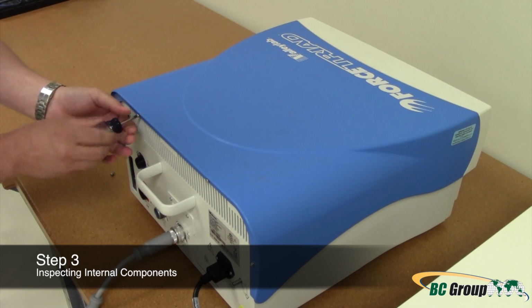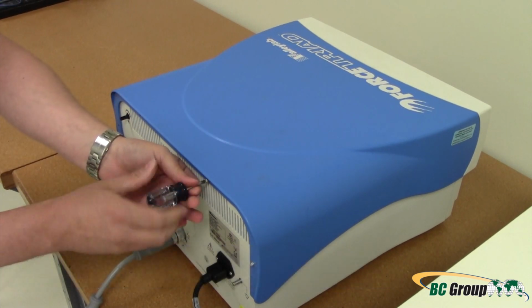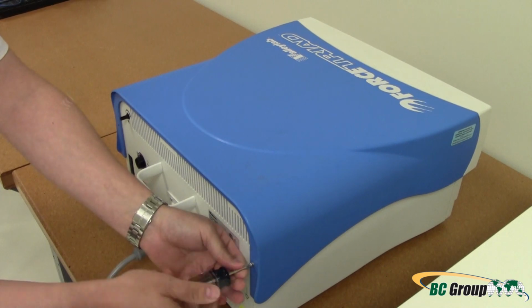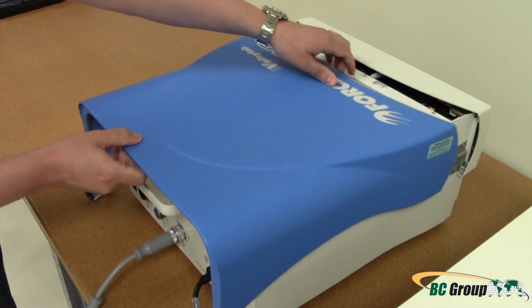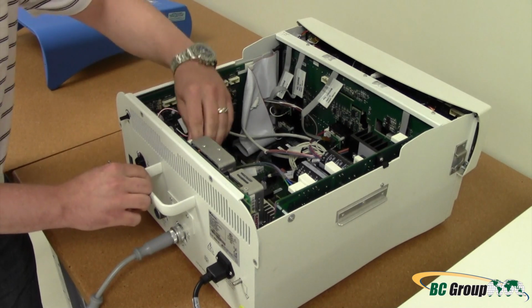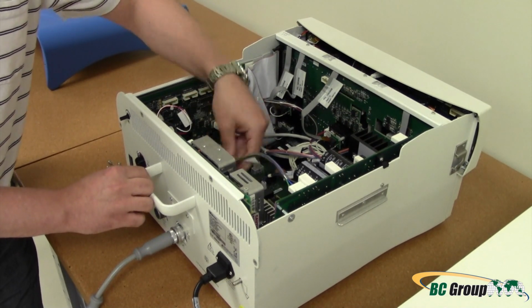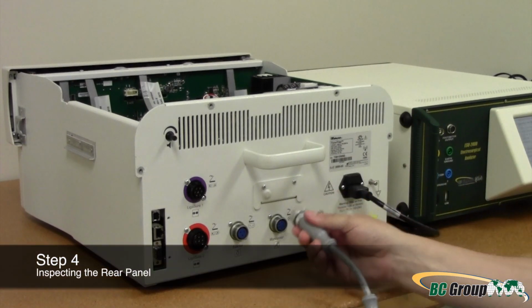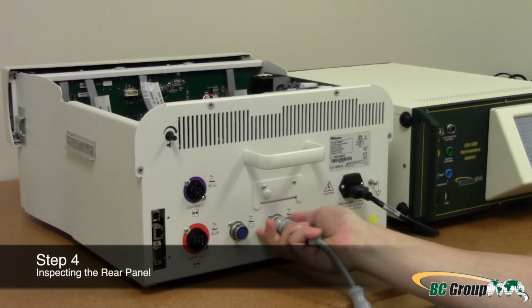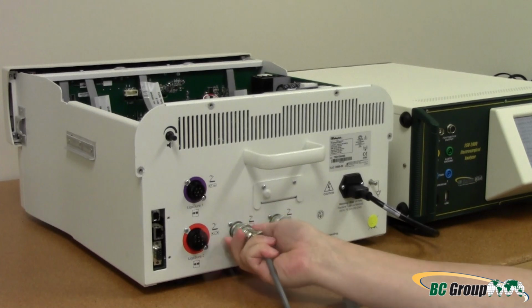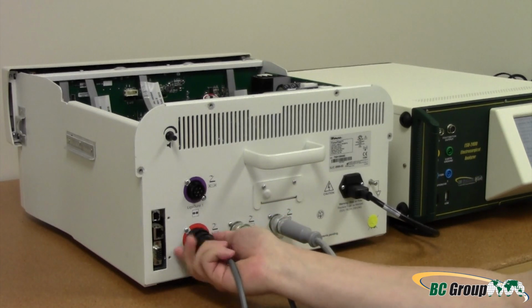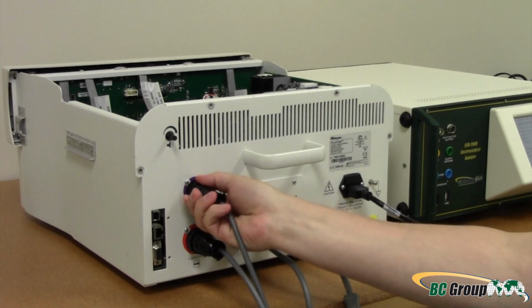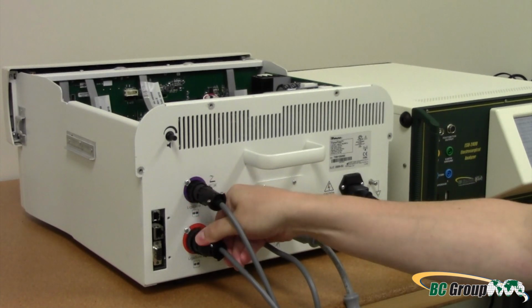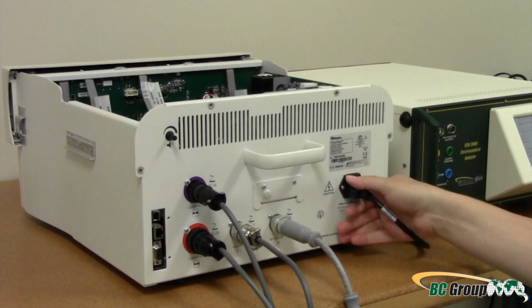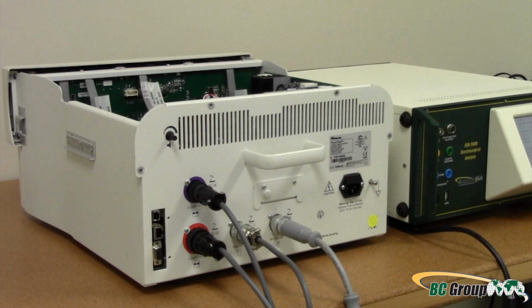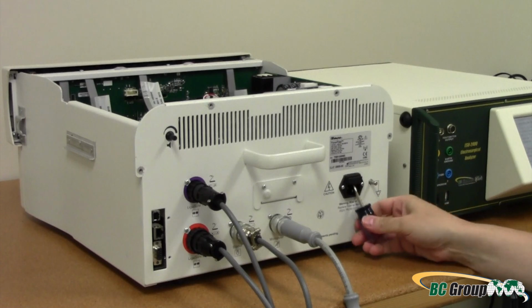Step 3. Inspecting internal components. Ensure that the generator is off. Remove the 4 screws that secure the cover to the chassis. Slide and lift the cover off the chassis. Verify that all internal connections are firmly seated. Step 4. Inspecting the rear panel. Check the rear panel connectors for obstructions or damage. Check for a secure fit by inserting the foot switch connector into each receptacle. Remove the fuse and verify correct voltage and current rating as stated in the service manual.